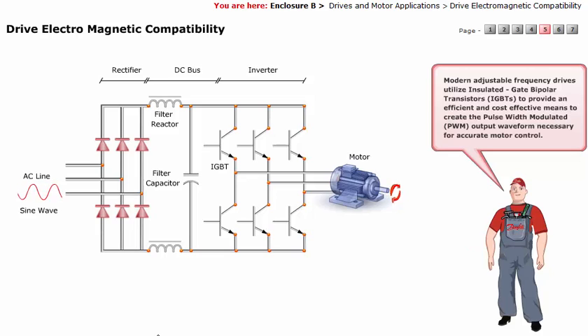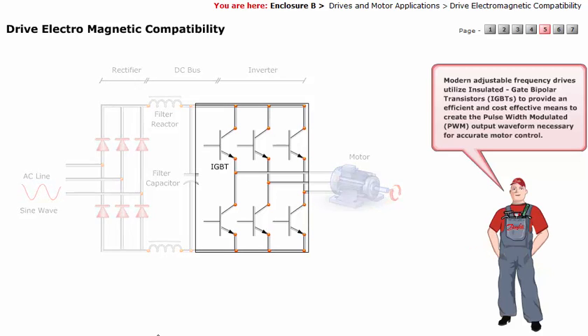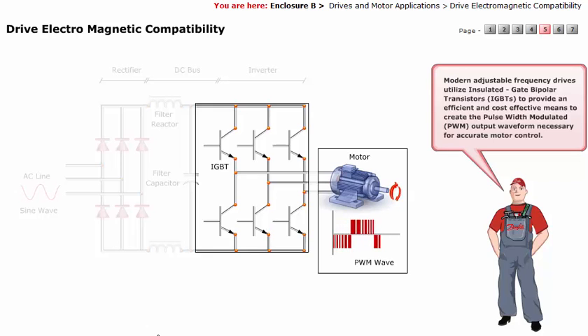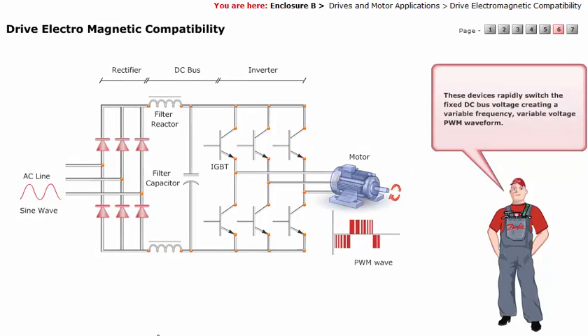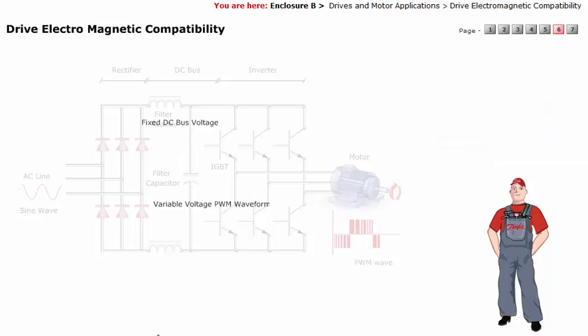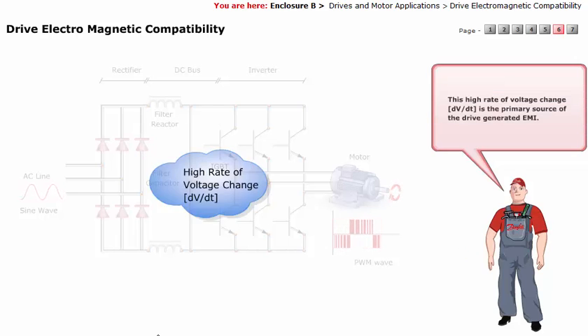Modern adjustable frequency drives utilize insulated gate bipolar transistors (IGBTs) to provide an efficient and cost-effective means to create the pulse width modulated (PWM) output waveform necessary for accurate motor control. These devices rapidly switch the fixed DC bus voltage, creating a variable frequency, variable voltage PWM waveform. This high rate of voltage change, dV/dT, is the primary source of the drive-generated EMI.